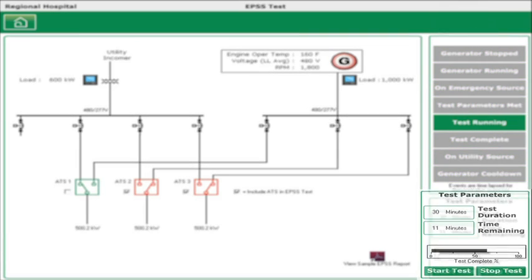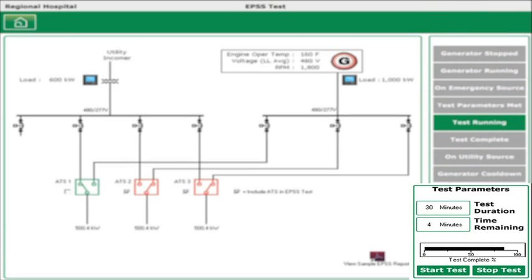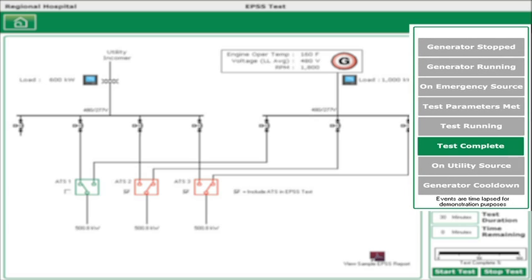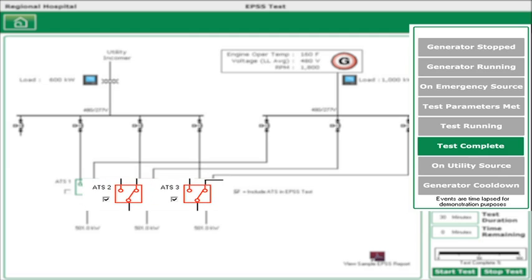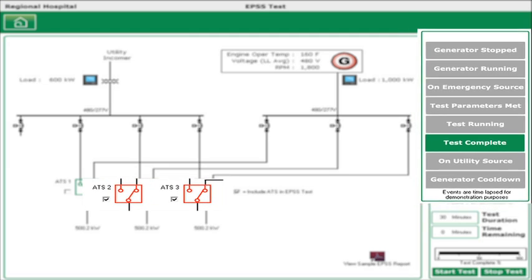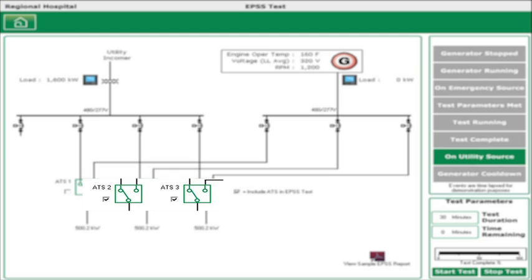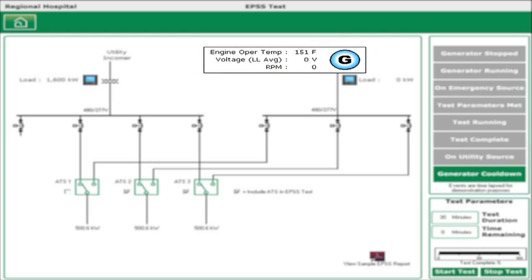As the test continues, the test parameters section shows the time remaining is running down. Once the specified time is elapsed, the test is complete. All recorded test data is automatically written to the database. As soon as the test is complete, the ATSs are switched back to utility power either directly or through the software. At this point, the generator begins its cool-down cycle, which marks the end of the testing process.